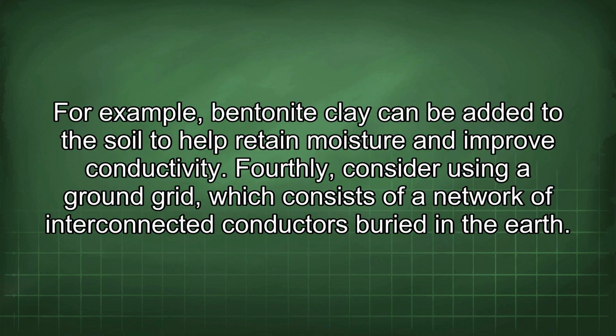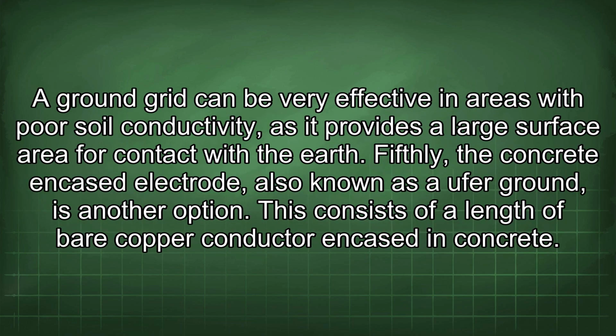For example, bentonite clay can be added to the soil to help retain moisture and improve conductivity. Fourthly, consider using a ground grid, which consists of a network of interconnected conductors buried in the earth. A ground grid can be very effective in areas with poor soil conductivity, as it provides a large surface area for contact with the earth.